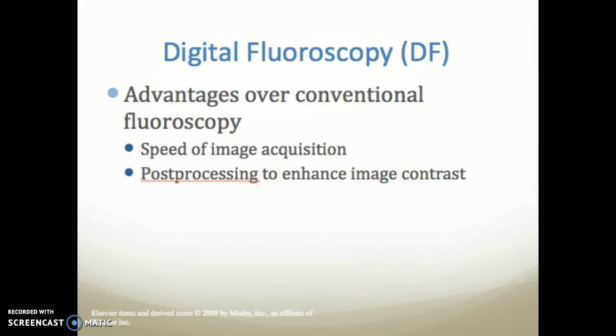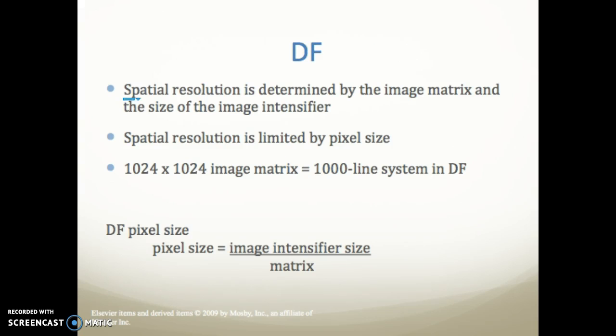Digital fluoroscopy has some advantages over conventional fluoroscopy. One is the speed of image acquisition and post-processing to enhance image contrast. With digital fluoroscopy, spatial resolution is determined by the image matrix and the size of the image intensifier. The spatial resolution is limited by the pixel size. A 1024 by 1024 image matrix is considered to be a thousand-line system in DF. When calculating pixel size, you take the image intensifier size — 6, 9, 12, or whatever the size — and divide it by your matrix.